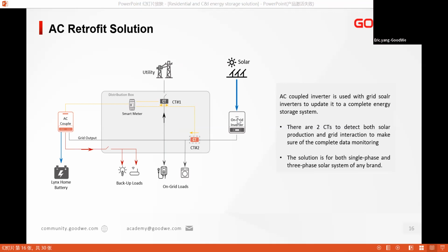Yes, we can, because in this system the on-grid inverter is connected to the grid directly, and it's also connected to the AC coupled inverter's grid output. Both the on-grid inverter output and the GoodWe AC coupled inverter output meet the requirements of the local grid — for example, we have certification from IEC or others.